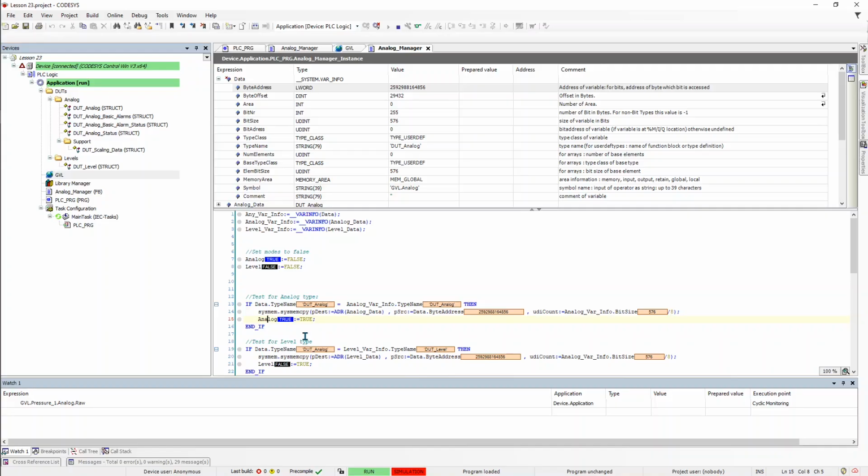So you can use temporary variables. The problem with temporary variables is they either introduce jitter to the PLC when you're online monitoring, or in Codesys' case, you can't monitor them very easily because they're not retained between scans, so you end up with question marks and you can't see the values. You can put flow monitoring mode on, which can help, but even flow monitoring doesn't show them in all cases.